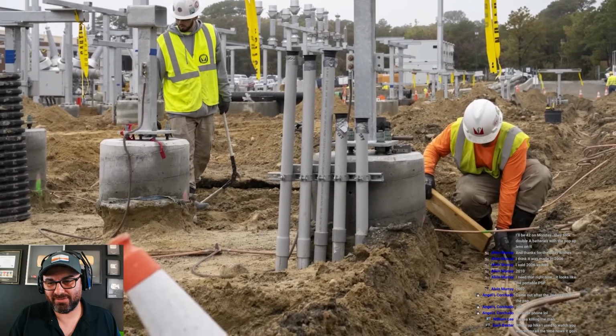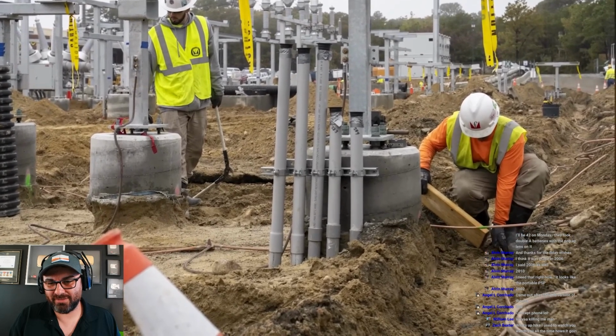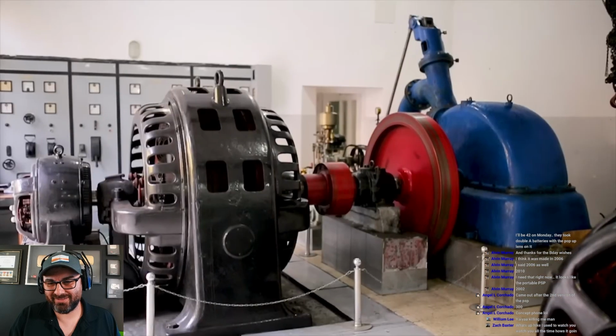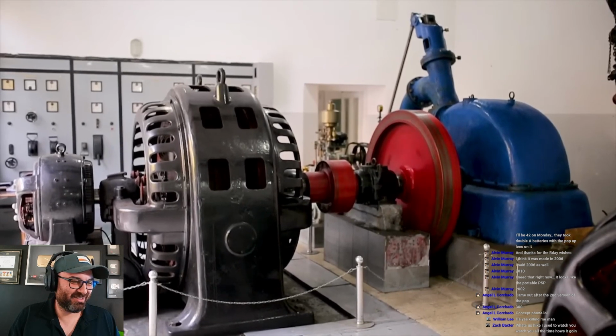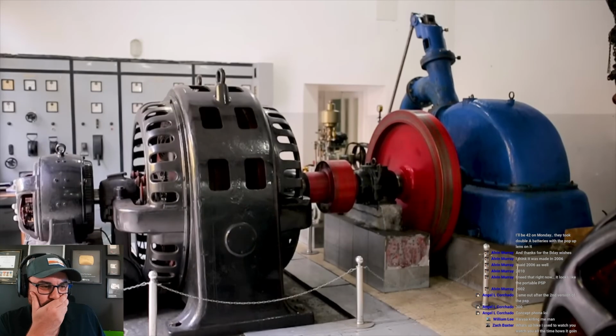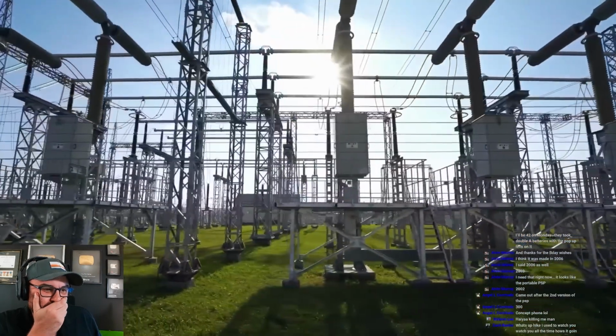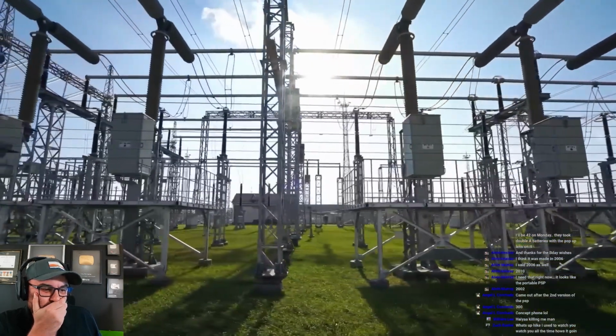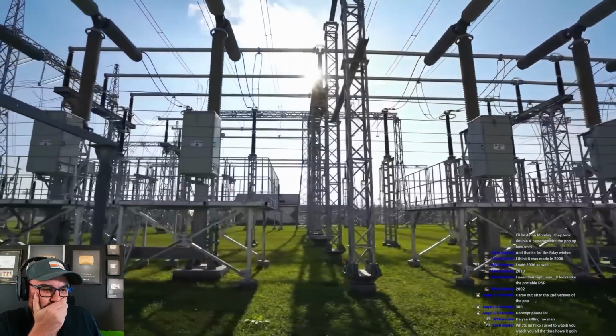Current doesn't flow to the ground, it flows through the ground and back up. If there is electricity moving into the ground from an energized conductor, go back to the source of that conductor and see what's happening. For the grid, it's probably a transformer or electrical generator, in either case a simple coil of wire. And the electrical current flowing out of the coil has to be equal to the electrical current flowing into it, whether that current is coming from one of the other phases, a neutral line, or an electrode buried in the ground.